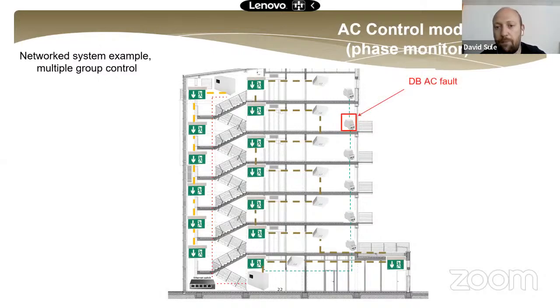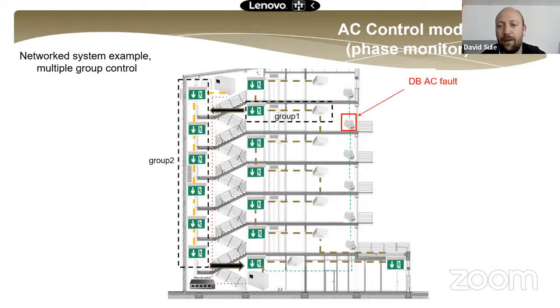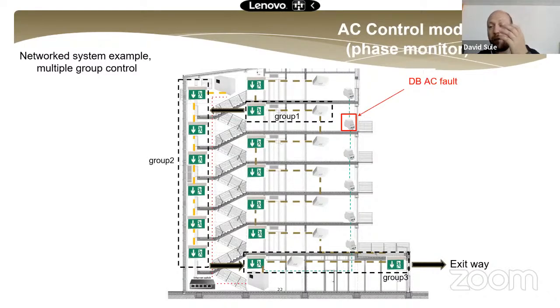And the power failure happened on 1 floor. This module sends information to the ground floor panel, and the ground floor panel will send network information to all of the networked panels in the building, and the 3 programmed groups will activate from 1 sub DB failure. So we can see the staircase lights are powered up by another panel, but it's connected to the Ethernet network switch, and the information came from the ground floor panel. The staircase light is activated by a simple AC control unit command.